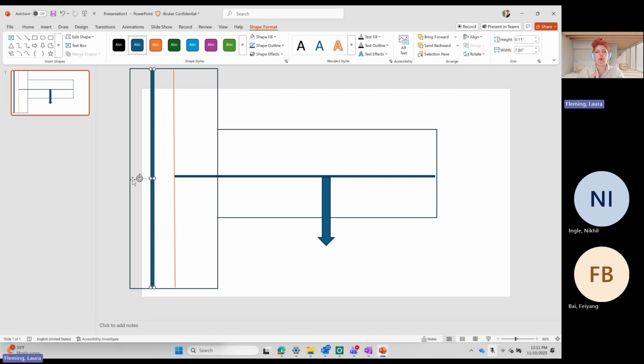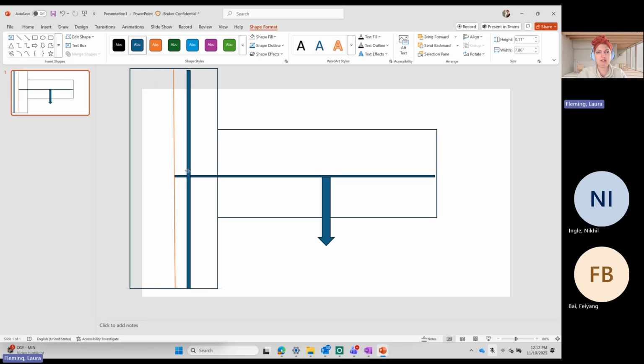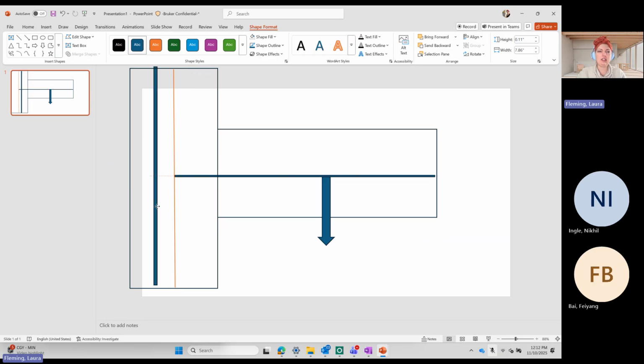So we're offsetting from the center point so that way when you do a scratch, for your system, I believe the maximum scratch is 15 microns. That is not 0 to 15. 0 to 15 would move the center plate from its imaging position of -10 to +5, thus moving it over to this other plate. What you need to understand is that it's 15 centered around 0. So it's -7.5 to 7.5 is your maximum range. And you're going to see this show up in the load function. So I just wanted to give us a quick introduction on why that exists.